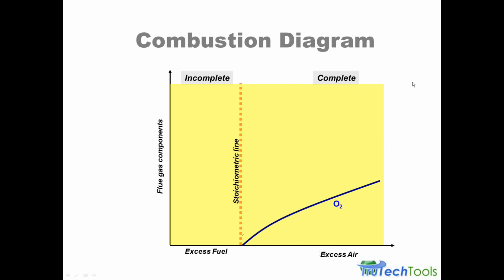So now we lay down the oxygen line. And an interesting point here is the oxygen line seems to emerge out of nowhere. There's no oxygen on the excess fuel side. Well, this is because all the oxygen available is being used up by the fuel in combustion, and there's nothing extra to go around. So this is an oxygen starved side, or incomplete, and now oxygen values start to appear. Again, we're looking at this probe being placed in the flue gas. The oxygen values start to appear and start to rise as you're looking at more and more excess air coming into the system.